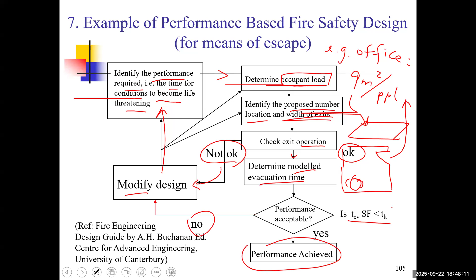Now, the TEVSF smaller than TLT is referring actually to this: the calculated evacuation time measured from the ignition of the fire, and we have a safety factor, okay, which should be less than the time for condition to become life-threatening. Again, measured from ignition, okay? So we need to see, for example, for 1,000 occupants, the time for evacuation times the safety factor should be less than the time for the condition to become life-threatening.